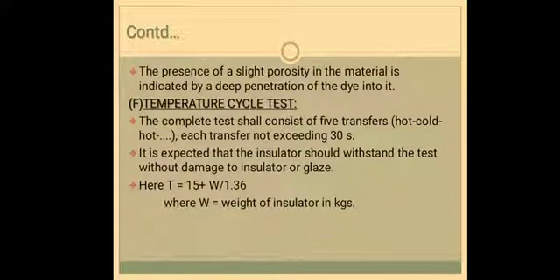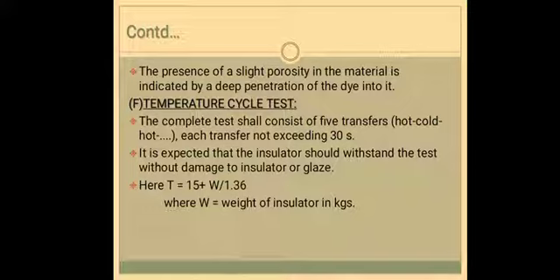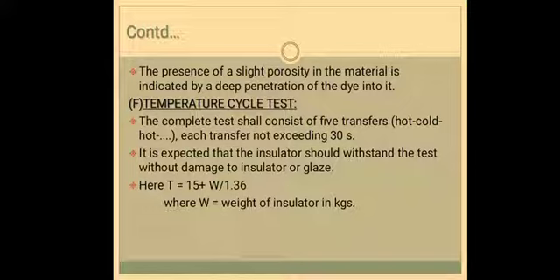Next will be the temperature cycle test. The insulator will be immersed in a hot water bath at a temperature 70 degrees higher than the normal water bath for 10 minutes. The complete test will consist of 5 transfers — that is from hot to cold, cold to hot and again from hot to cold. Each transfer will not exceed 30 seconds, and it is expected that the insulator should withstand the test without damage to the insulator or glaze. Here, T minutes is equal to 15 plus W divided by 1.36, where W is the weight of the insulator in kilograms.